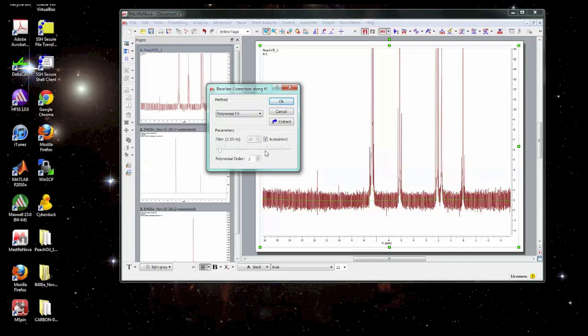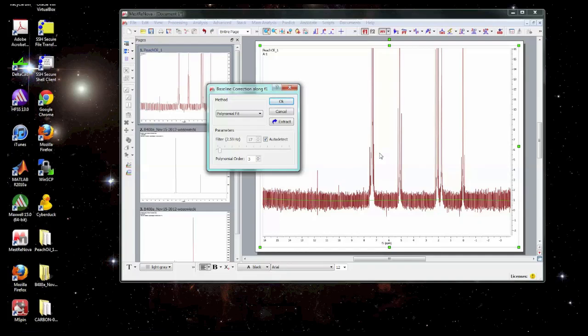Polynomial fit is a much more conservative form of baseline correction. This filter corresponds to the width that it uses to remove data that it considers a peak. So what it wants to do is fit only the baseline and ignore the peaks. What you wouldn't want is for this baseline to try to go up and down through the peaks. So this filter, the wider it's set, the broader of a feature in the spectrum that it will assume is a peak and ignore from the spectrum. Normally the auto detect works pretty well.